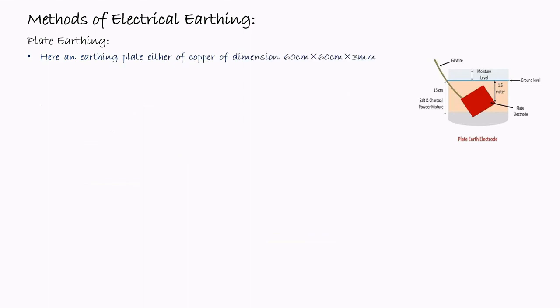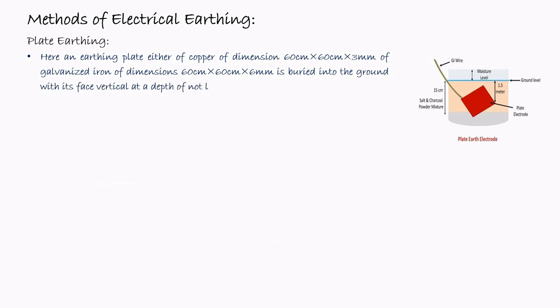Here an earthing plate, either of copper of dimensions 60 centimeter by 60 centimeter by 3 millimeter, or of galvanized iron of dimensions 60 centimeter by 60 centimeter by 6 millimeter, is placed into the ground with its face vertical at a depth of not less than 3 meters from the ground level. So here we can see this plate is placed vertically in the ground and the length from one side is around 1.5 meter.